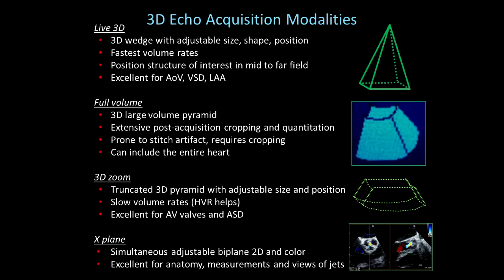3D Zoom is the third acquisition modality — a truncated 3D pyramid with adjustable size and position. It works very well for horizontally oriented structures but tends to have a very slow volume rate. Volume rate is the same as frame rate; in 3D we say volume rate. HVR is a setting on the 3D ops button — that's high volume rate — which can mitigate some of the slow volume rates encountered with 3D zoom.